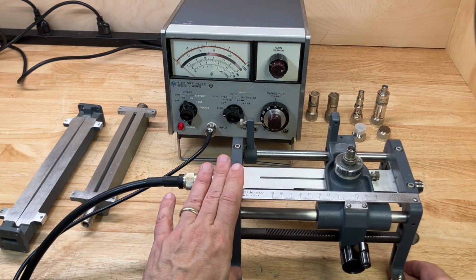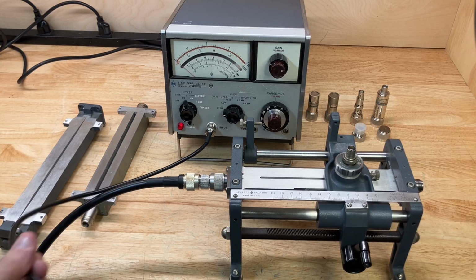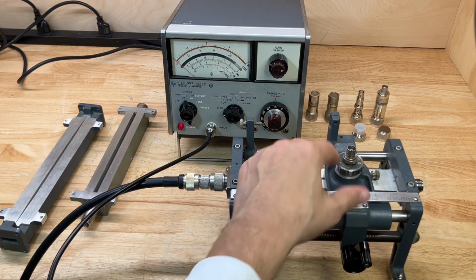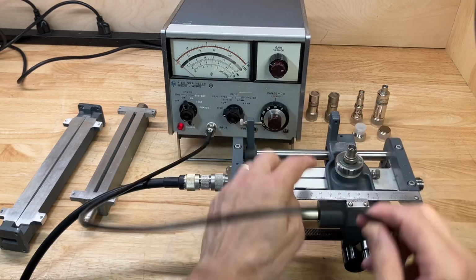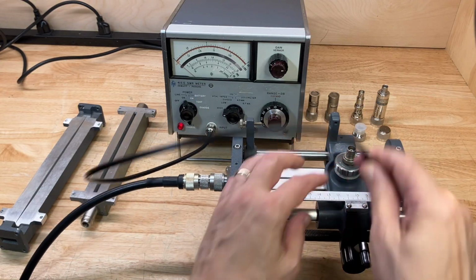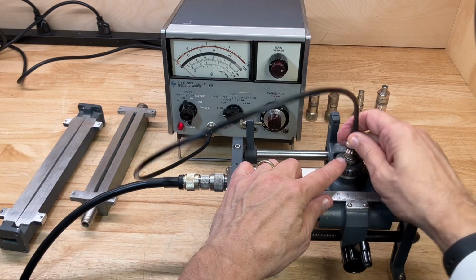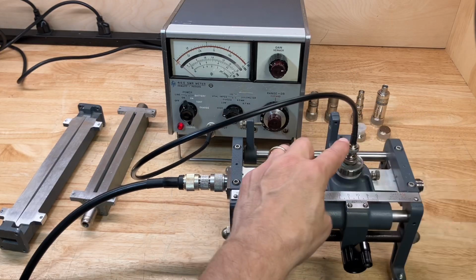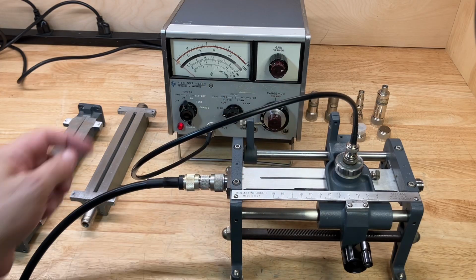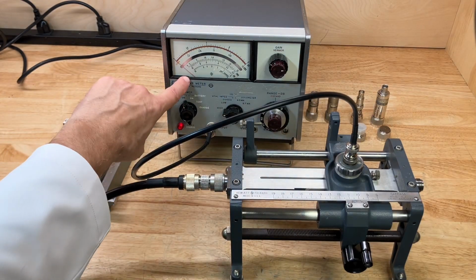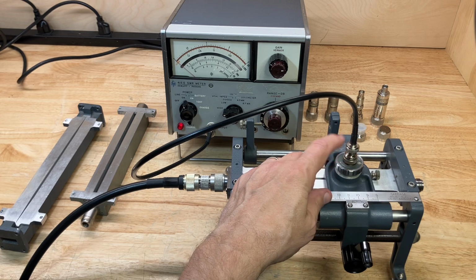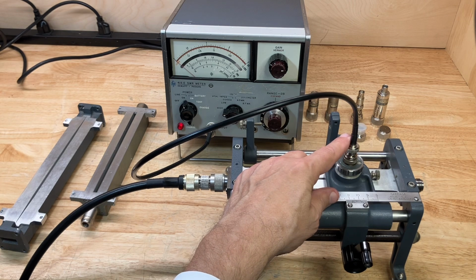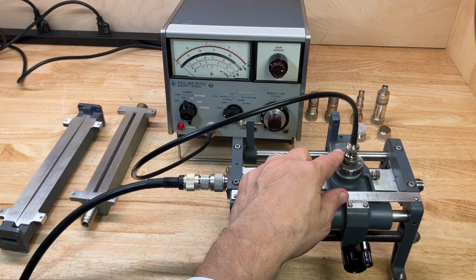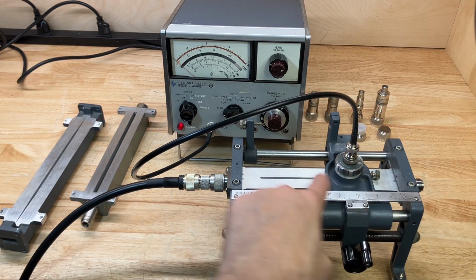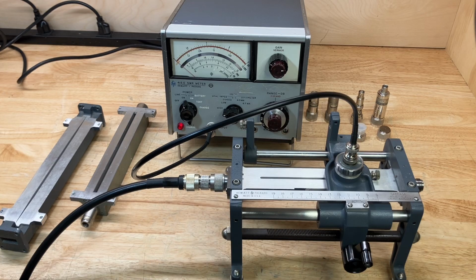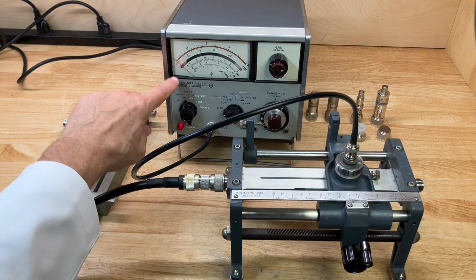So we're going to make an SWR measurement. The output of the 444A probe, which has a crystal detector inside of it actually, is the detected AM modulation at 1 kilohertz. It comes out of the BNC connector at the top, and that will go into our 415E. And from that, that detected 1 kilohertz sine wave will be the proxy that indicates the relative amplitude of the RF signal inside the slot in the slotted line, as detected by the probe and indicated on the 415E.